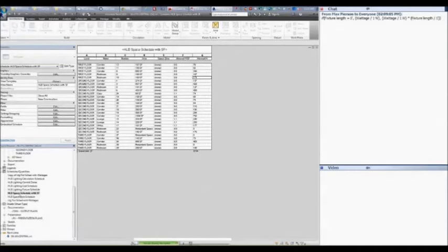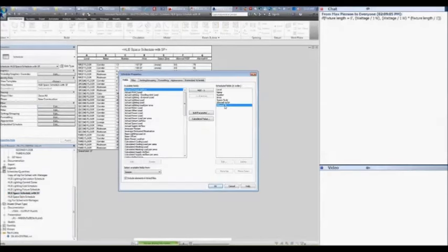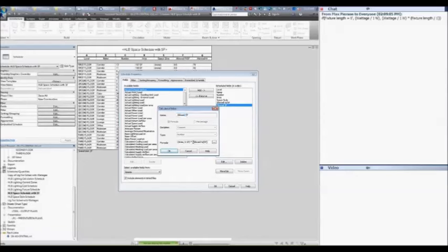And then it's a very simple formula. Okay, so the formula is area, divided by one square foot, because you have to remove the units or it will throw an error, and then it's the allowed watts, which also had to be divided by square foot.